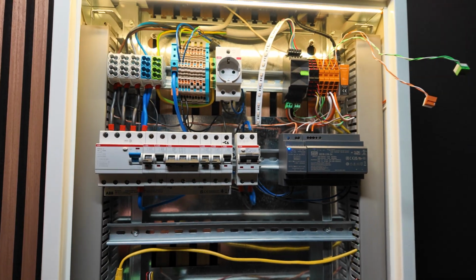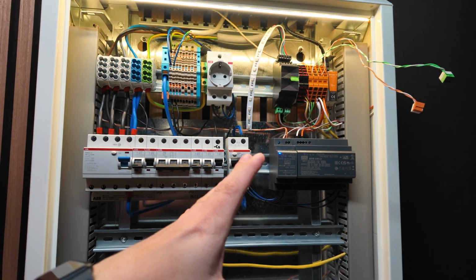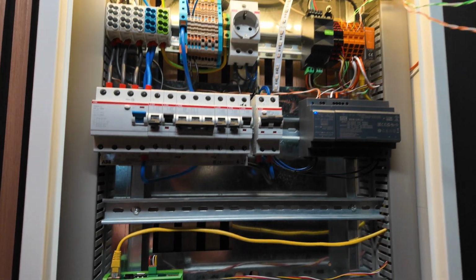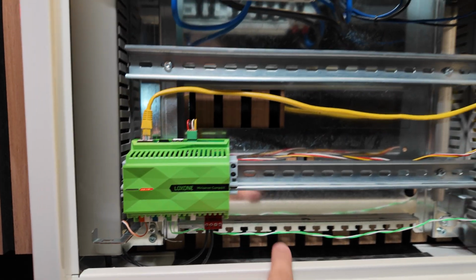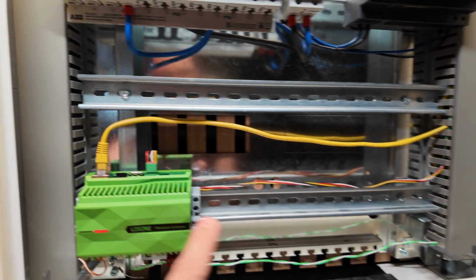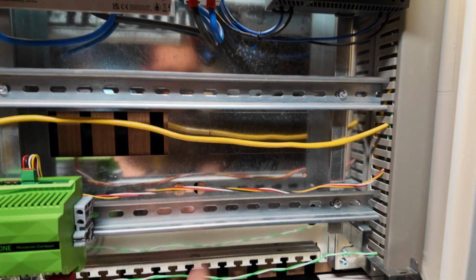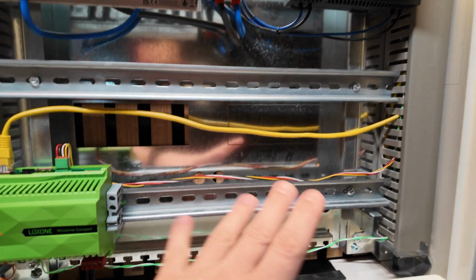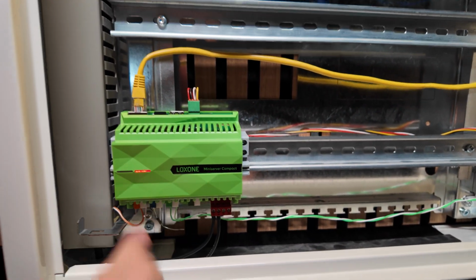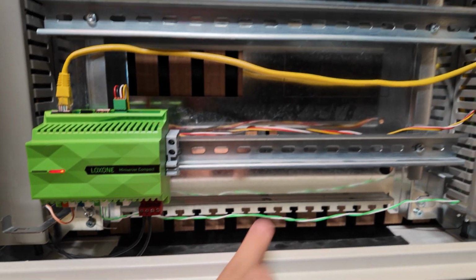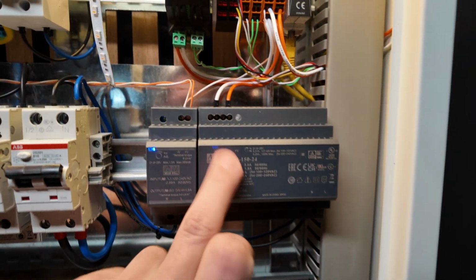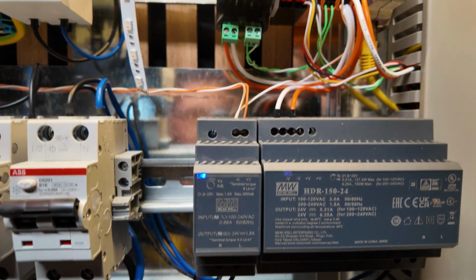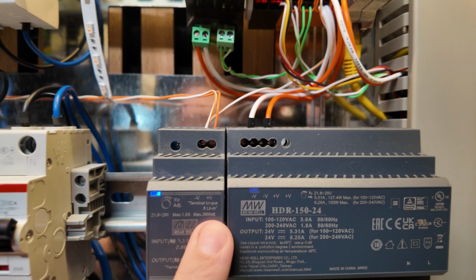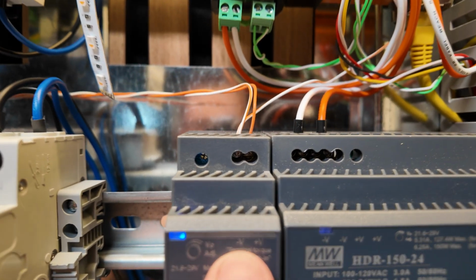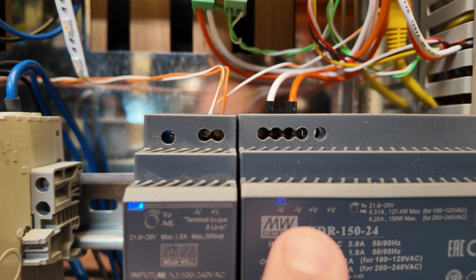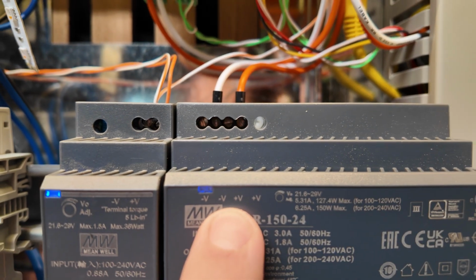All the blinds go up, or when the alarm system is blinking all the lights in the house, what is happening? The Miniserver sends lots of commands also to the extensions. Relay extension number 3, relay 2, 4, 5, turn on, turn off, turn on, turn off. So when lots of traffic is going on, then this mistake of not connecting the grounds is making problems. Which is super simple to fix. You simply connect the minus from this one to the minus of the other power supplies in the system.